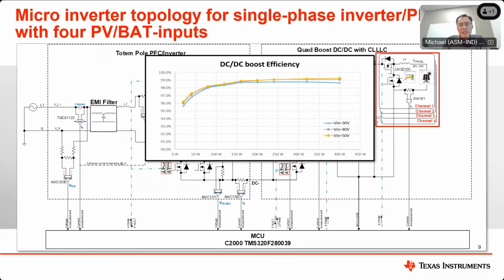When we look at the first stage, we can see the efficiency versus input power applied from the panel. The 3 different graphs represent different input voltages to the DC-DC boost stage. Over a very wide range, the efficiency is way above 98.5%, even for low input voltages of only 30 volt.